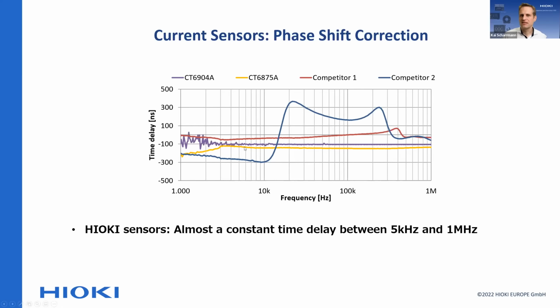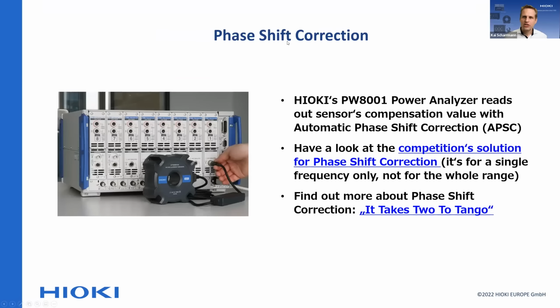And you can see from the Hioki sensors, and that's really where it matters, that there is almost a constant time delay between 5 kilohertz and 1 megahertz. The 5 kilohertz is where it really matters in power analysis for higher frequencies. And to be honest, at 1 kilohertz, the jitter that you see at 100 nanoseconds doesn't really make a difference. So, summarizing phase shift correction: the PW8001 power analyzer reads out the sensor's compensation value automatically when you plug it in. As it reads out the serial number and the conversion ratio, or the voltage ratio, it also reads out the phase shift correction value. That's what we call automatic phase shift correction in our PW8001 power analyzer.